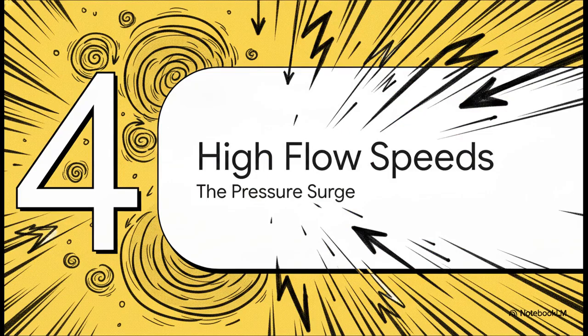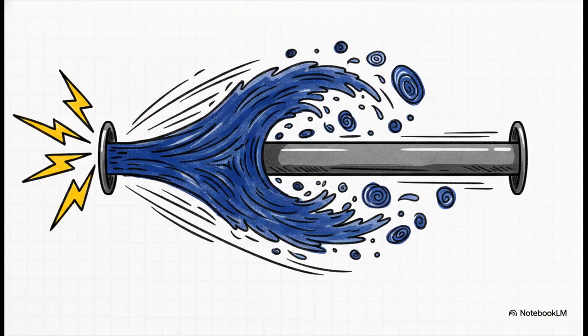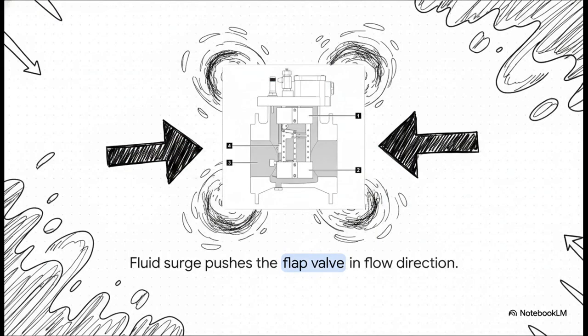Section 4. Stopping high flow speeds, the pressure surge. What happens if a major internal short circuit or fault hits? It can create this massive, explosive pressure wave. This wave literally forces the insulating oil to rush toward the conservator tank at crazy high speeds, way over the standard safe limit of 100 cubic centimeters per second. When that happens, that sudden, violent rush of fluid physically slams right into that small flap valve suspended in the middle of the pathway. The immense force of the surge pushes the flap violently in the direction of the flow.